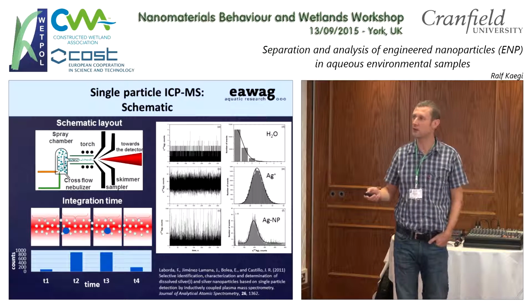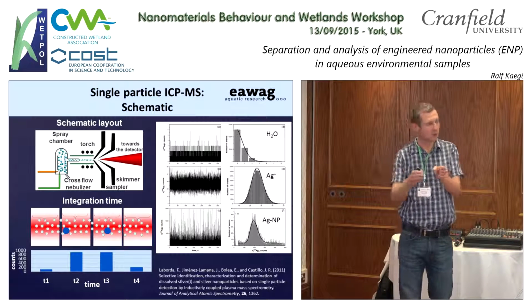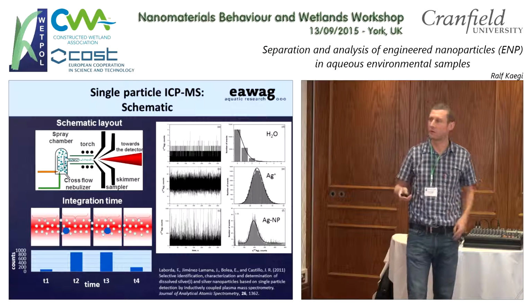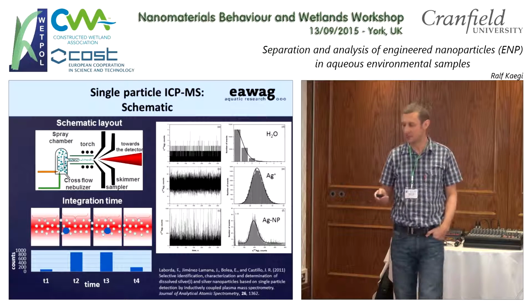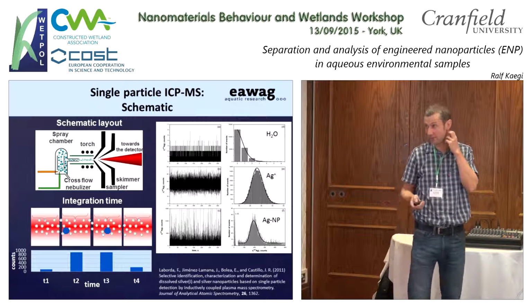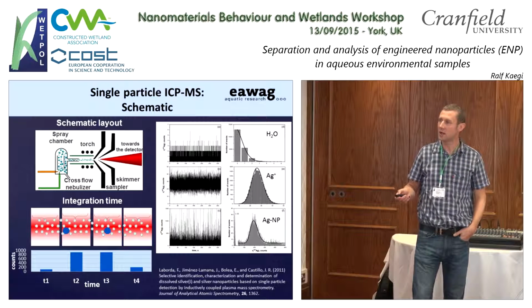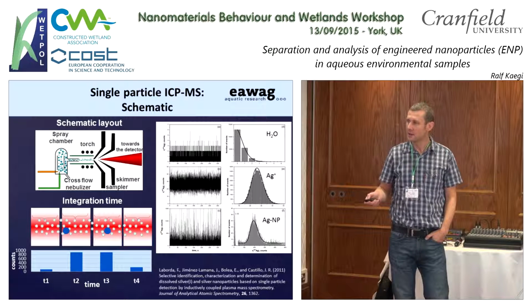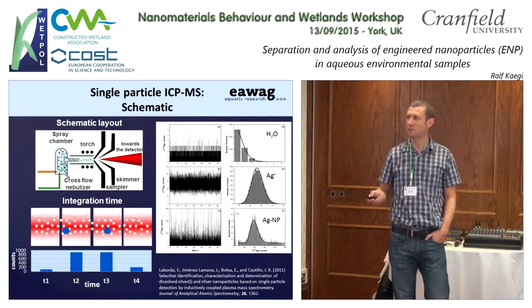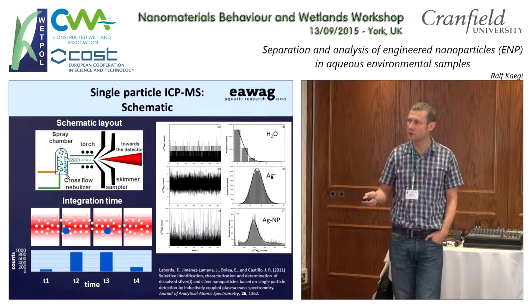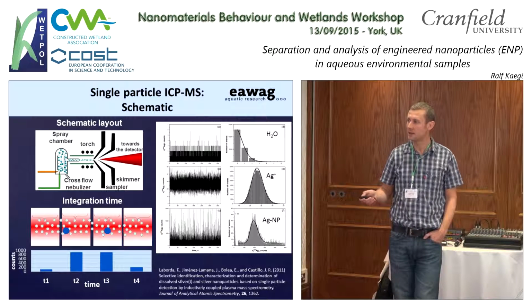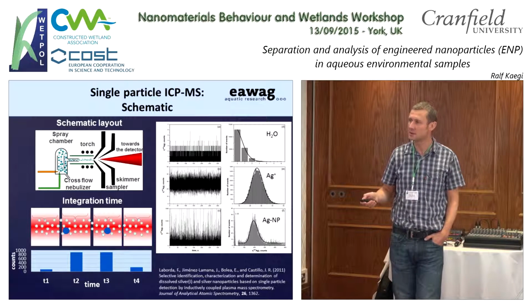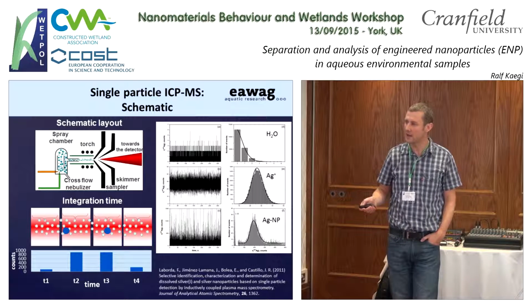When you go in single particle mode, you have very small integration times in the order of a few milliseconds, classically 5 to 10 milliseconds. Also newer devices are faster. What you aim for by adjusting the dilution, you have a package where you analyze where you have no particles, then you have a particle, and you have no particle.